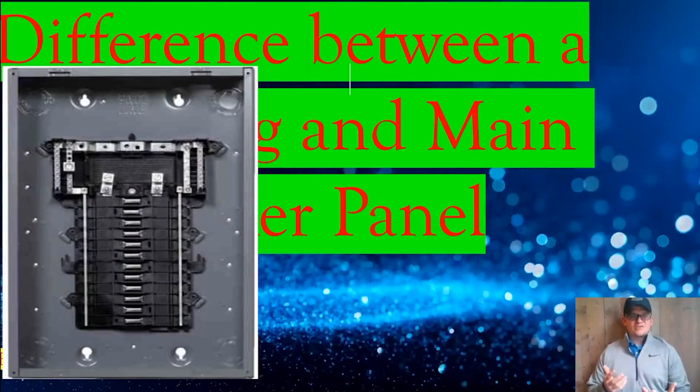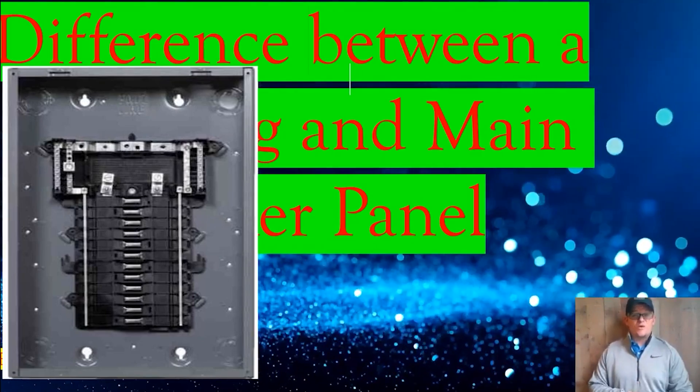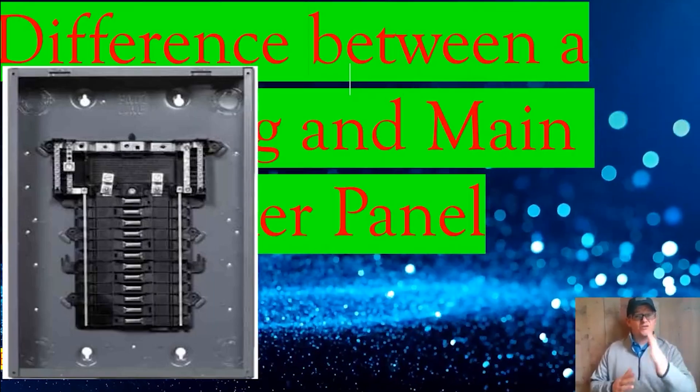So let's look at the main lug first. A main lug panel is just like it sounds. It has no breaker installed. It's literally just going to have the lugs up at the top that you terminate the main wires to. These are great for feeder panels, anywhere that's past the first point of disconnect.